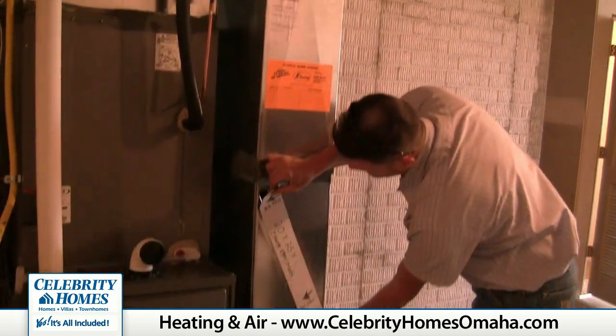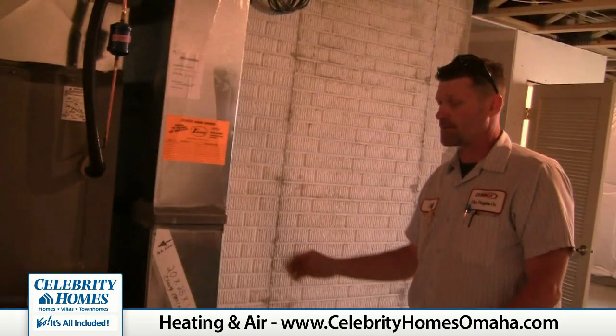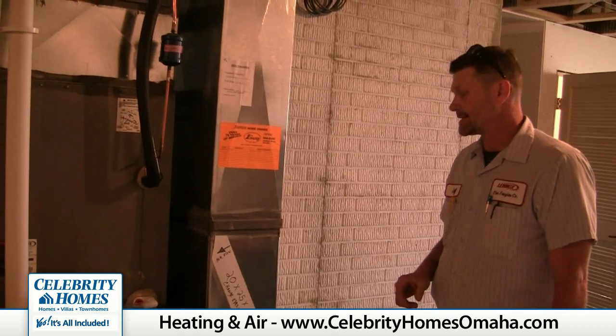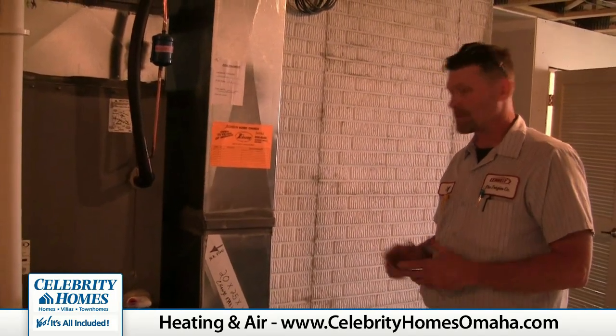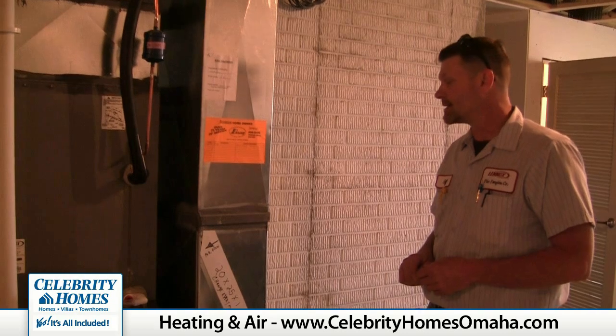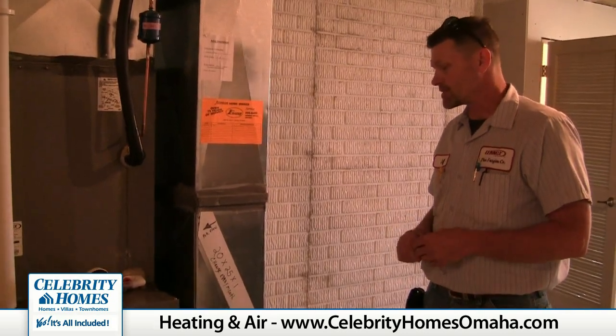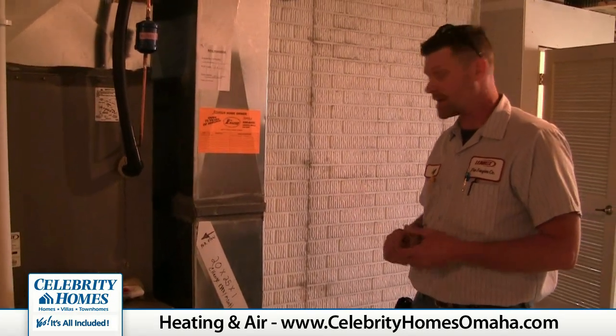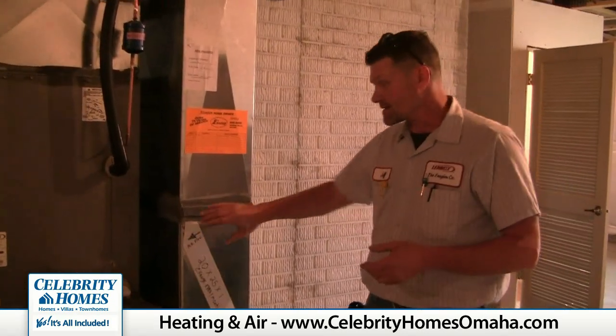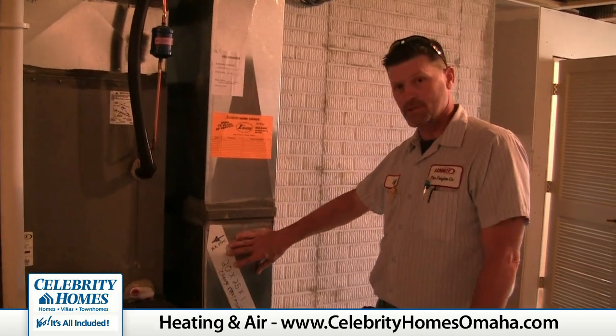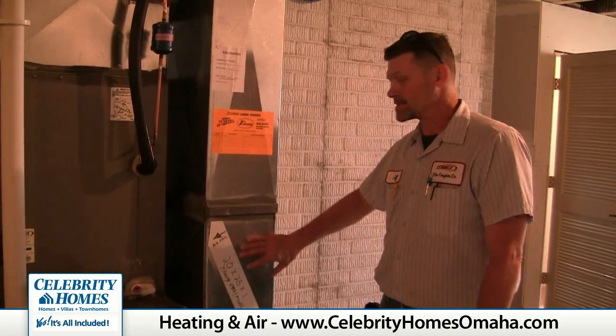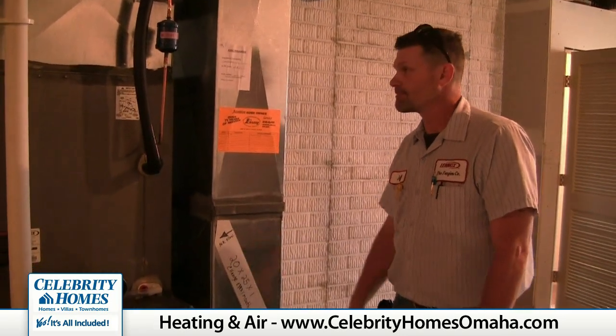The rule of thumb is to check the filter every 30 days. You can purchase filters out there on the market now that say that the filter is good for 90 days. That may not always be the case. It depends on how often you run the equipment, the heating, the cooling. It may last 90 days, it may not, but the general rule of thumb is to check it every 30 days and just replace it if necessary.